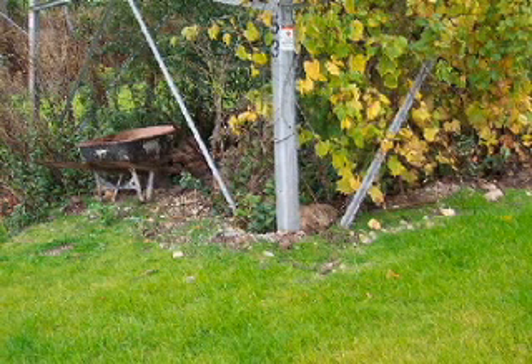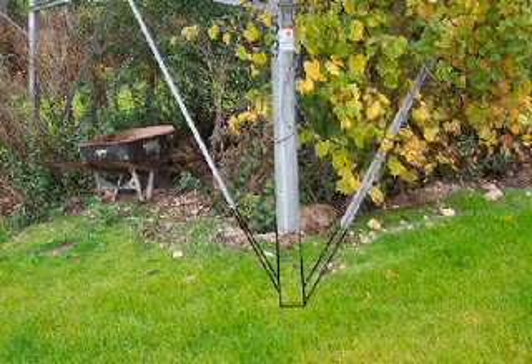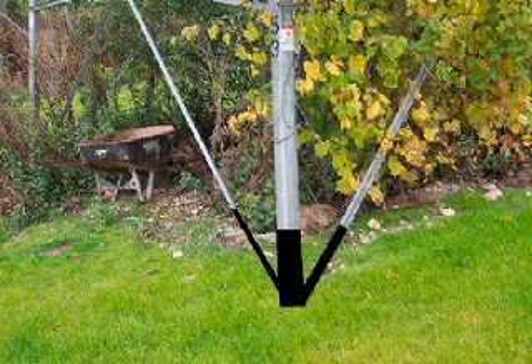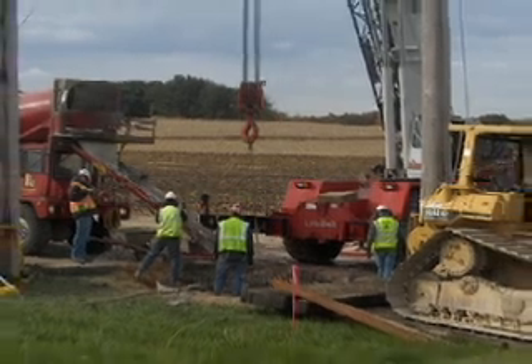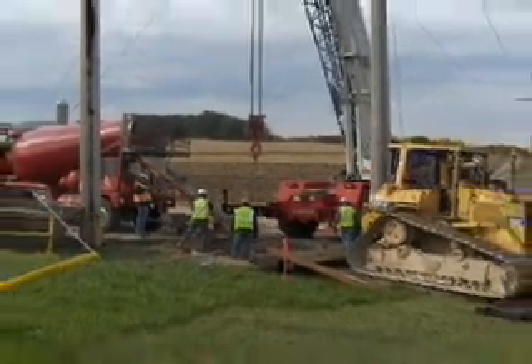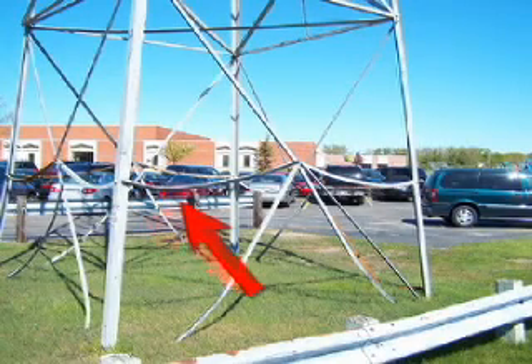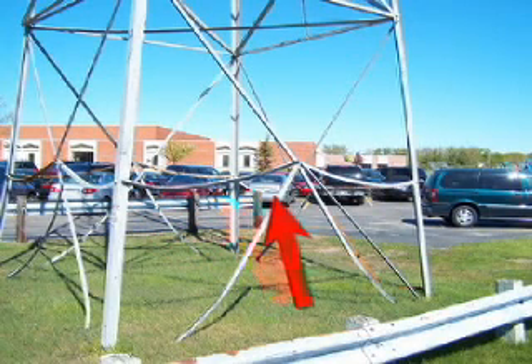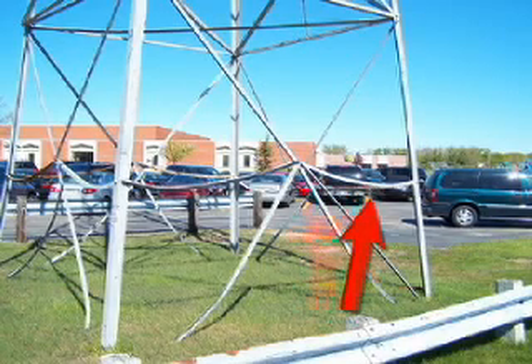The buried portion of a transmission structure is treated with a special protective coating that guards against corrosion. The portion of transmission poles that are below ground are specially treated to prevent decay. When a portion of a structure that is meant to be above ground is covered with fill, the moisture in the soil can cause corrosion and weaken steel poles or cause wood poles to rot. In addition, use caution when driving near transmission structures. Damage caused by contacting the structure with equipment or vehicles can reduce the strength of the structure.